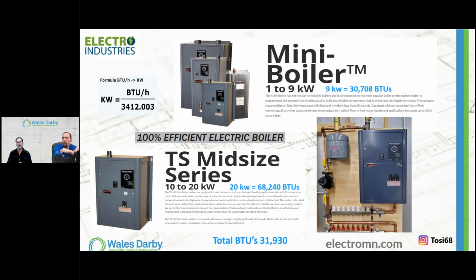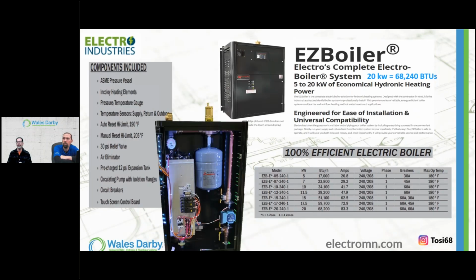These slides are a little bit old. I haven't updated them, but this whole lineup of what Electro is offering with their standalone. This one is a packaged boiler, as you see in the photo. There are 4 connections, and I'm not here to harp, but man, think about the time savings, the labor savings. It's already packed. It's an appliance. You have a supply, you have a return. There's 2 connections. You have a relief valve. There's your 3rd connection. The 4th connection is your pressure reducing valve. It's the only thing that does not come in the box.